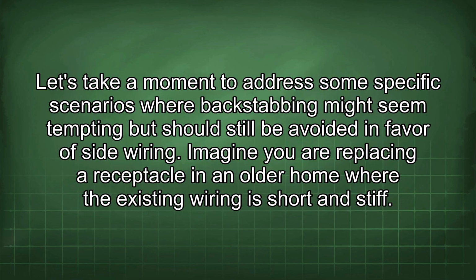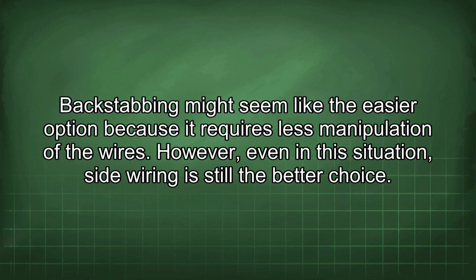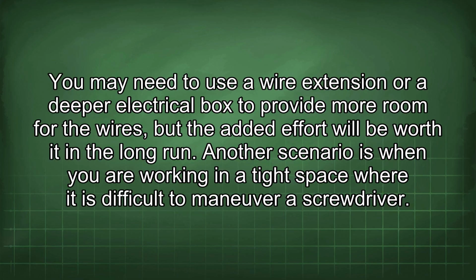Let's take a moment to address some specific scenarios where backstabbing might seem tempting, but should still be avoided in favor of side wiring. Imagine you are replacing a receptacle in an older home where the existing wiring is short and stiff. Backstabbing might seem like the easier option because it requires less manipulation of the wires. However, even in this situation, side wiring is still the better choice. You may need to use a wire extension or a deeper electrical box to provide more room for the wires, but the added effort will be worth it in the long run.